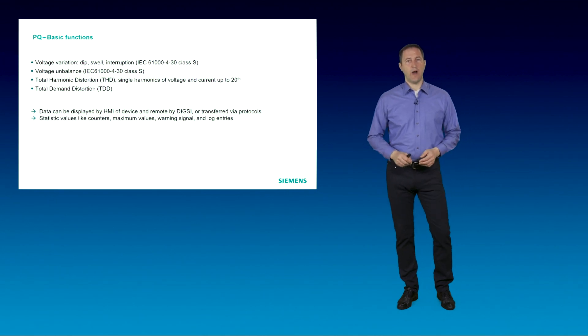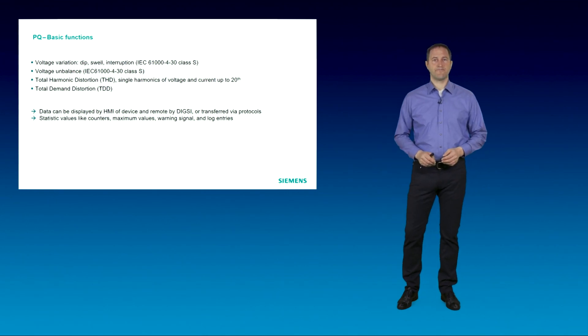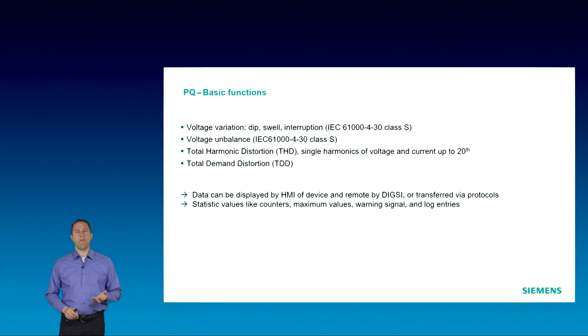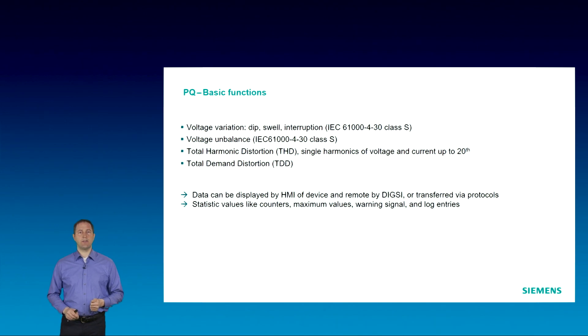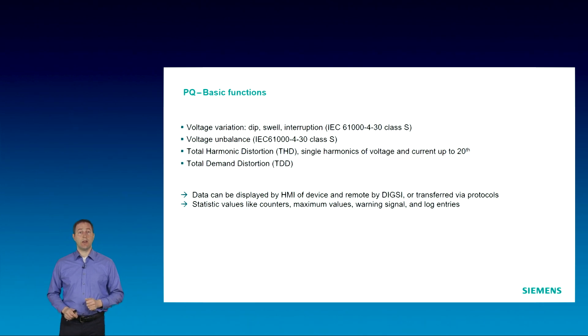PQ functions overview. It provides voltage variation — that is dips, swells and interruption — and voltage unbalances. These functions comply to the standard for power quality measurement IEC 61000-4-30 class S. And the total harmonic distortion, the THD.